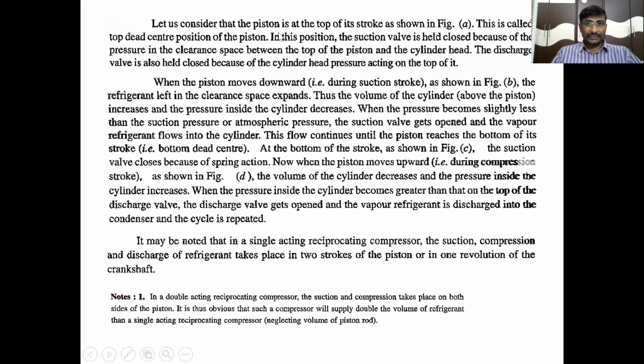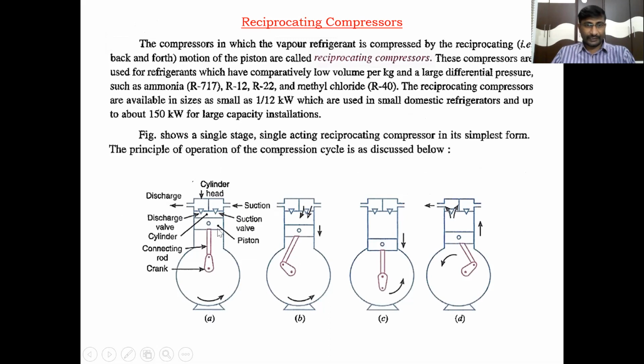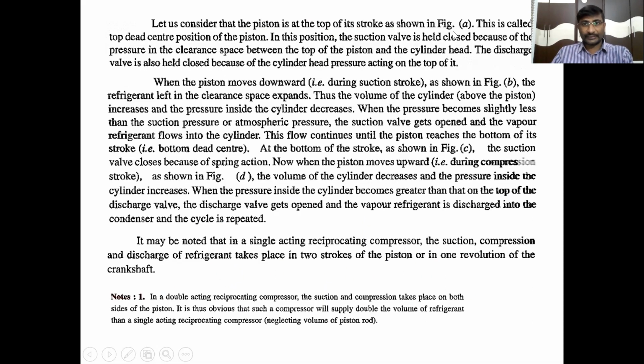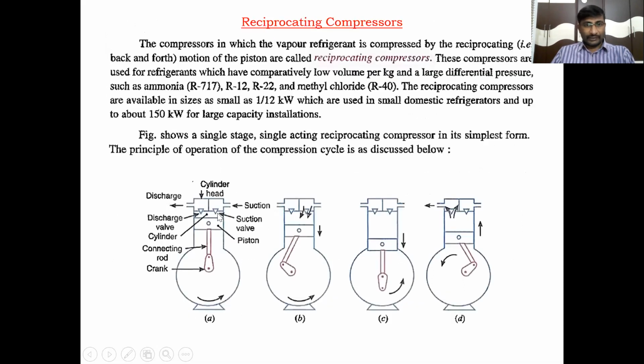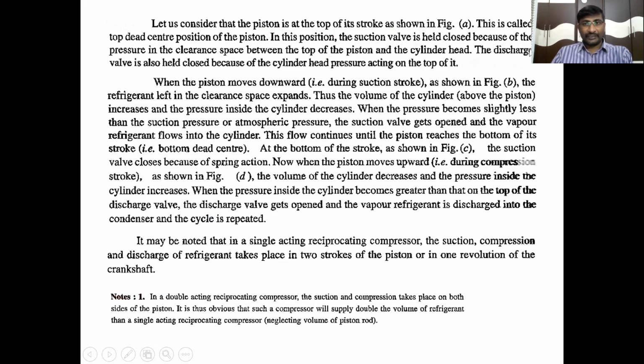Let us consider that the piston is at the top of its stroke as shown in figure A. When the piston is at the top position, this is called the top dead center position of the piston. In this position, the suction valve is held closed because of the pressure difference in the clearance space between the top of the piston and the cylinder head, because the pressure is very low in the cylinder before suction. The discharge valve is also held closed because of the cylinder head pressure acting on the top of it.